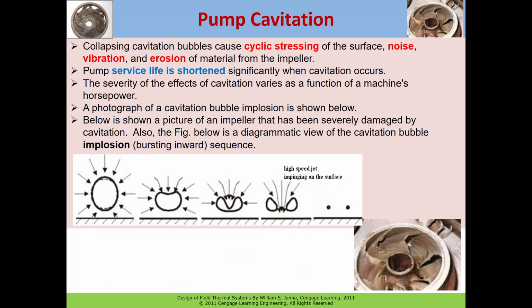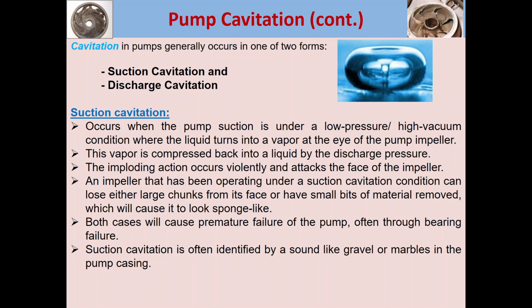So when we talk about the pump, there are three or four phenomena that cavitation creates: it creates noise, it creates vibration, it creates stress on the surface of the impeller, and it creates erosion. These are the outcomes or results of cavitation. When we talk about the pump, we categorize cavitation into two categories: the suction side cavitation and the discharge side cavitation.